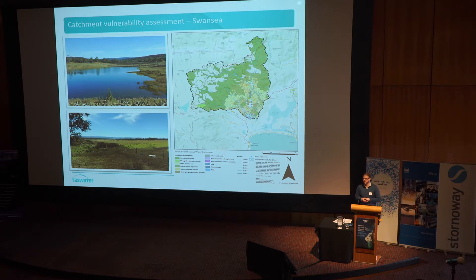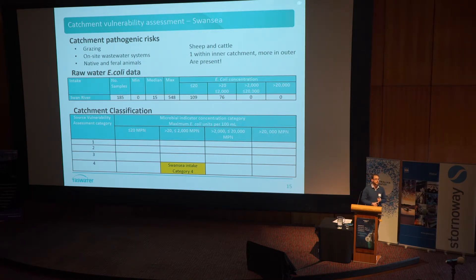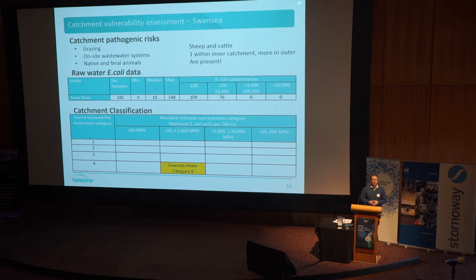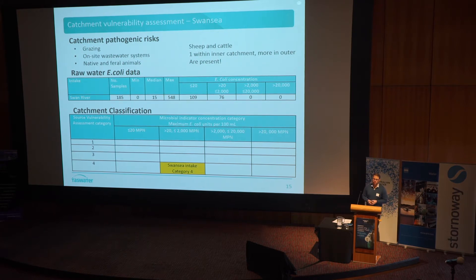These pictures were taken by people doing a catchment investigation on-site — they weren't as glamorous as some of the diving we saw earlier. These guys were looking for evidence of animals with pathogens that could infect people. With Swansea, our identified risks were: grazing with sheep and cattle in the catchment, at least one on-site wastewater system — and if you know anything about those, you have no idea how effective they are — plus native animals. That aligned us with a category four catchment. We then looked at our raw E. coli data — we had 185 data points, and our highest concentration was in the 20 to 2,000 E. coli range, which also put us in category four.